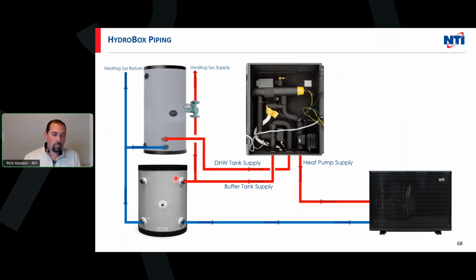So we have the heat pump supply coming out, and that's outgoing water, which comes in through the box. We have a circulator built in there. The diverter valve is then going to, based on the mode we're in, whether domestic or heating, divert that water either to the buffer tank or the domestic hot water tank. From there, we go into our heating system, our returns from both the indirect and the buffer tank, and they're going to go to the heat pump themselves. So that's what the hydro box looks like.